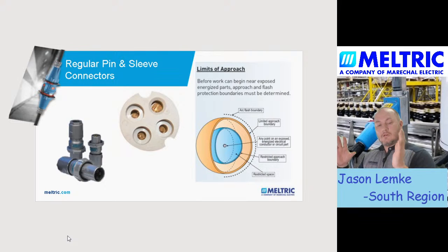So in the most stringent reading of the NFPA 70E, if I remove my plug from my receptacle and I'm using a pin and sleeve device, I will have exposed electrical conductors. Therefore, I will have a restricted space around that where only qualified people with their appropriate PPE, who understand the hazards of working around this exposed conductor, are able to work in that environment.